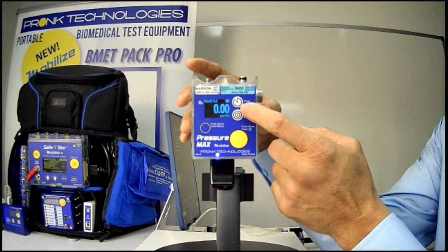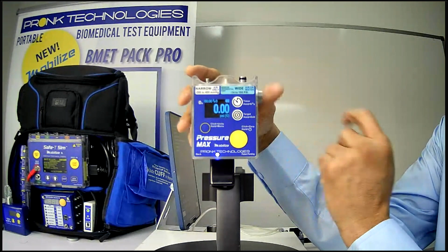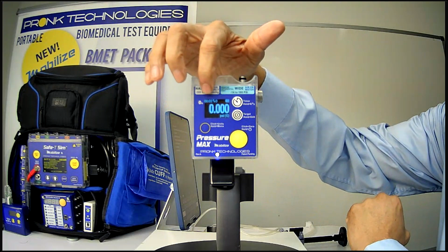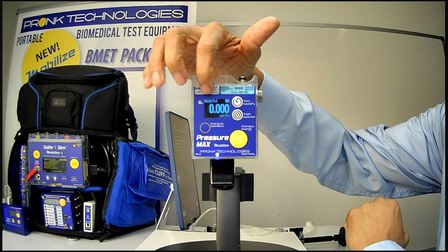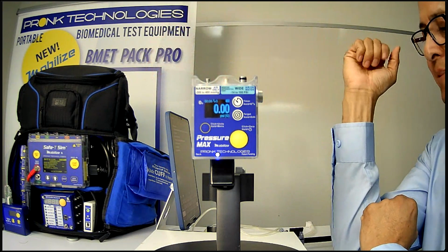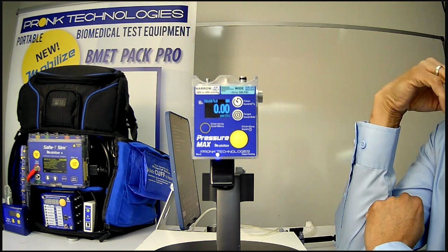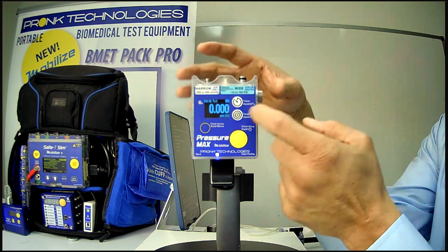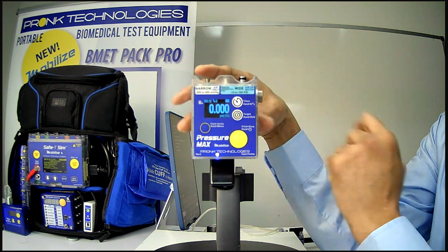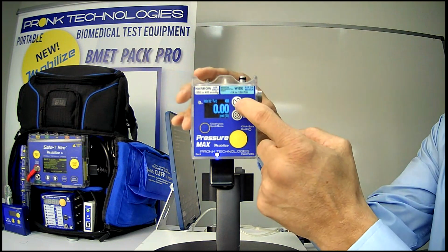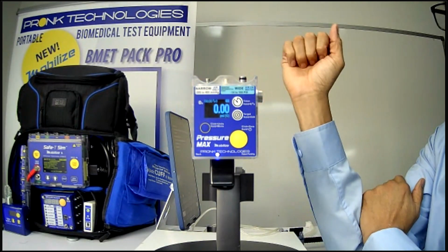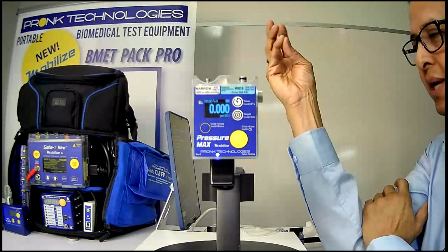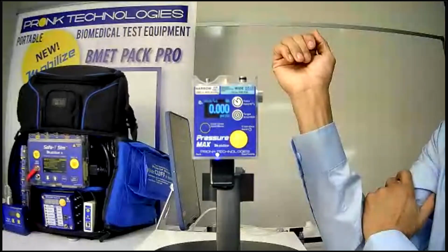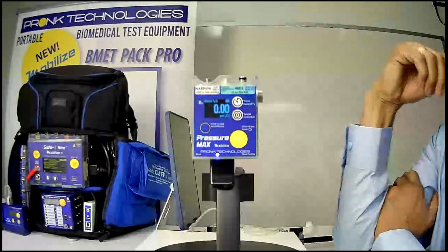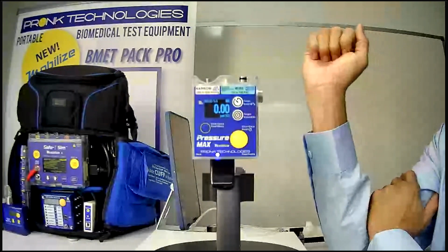To do that leakage test, you can simply press this button here. The timer in the upper left will turn on, and it will start capturing the elapsed time since we started the test. If you want to stop the timer, you can simply press the button here to stop the timer, and you can press it again to reset it back to zero. So it's a nice feature for doing leak tests or time tests where you want to know how long it took, what was that leak rate at that particular pressure.